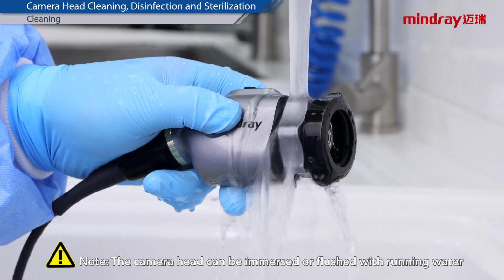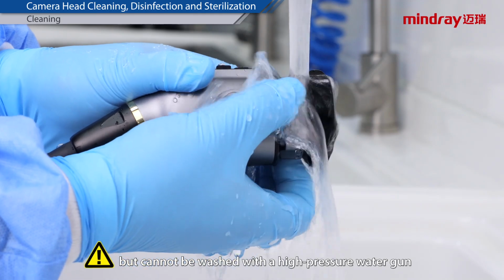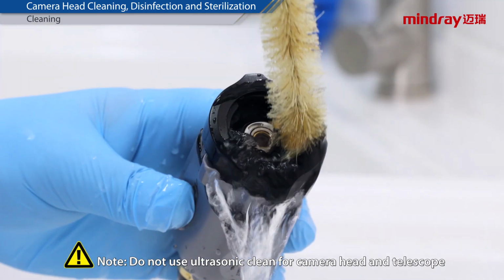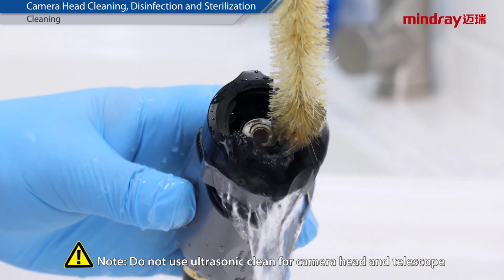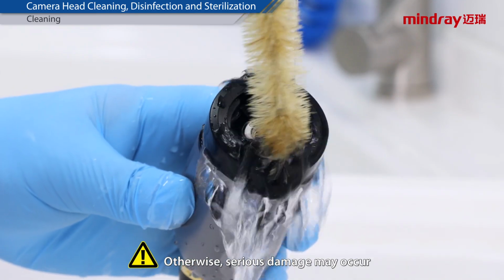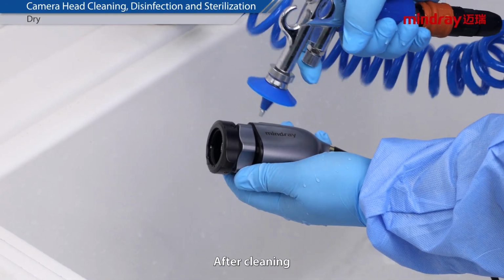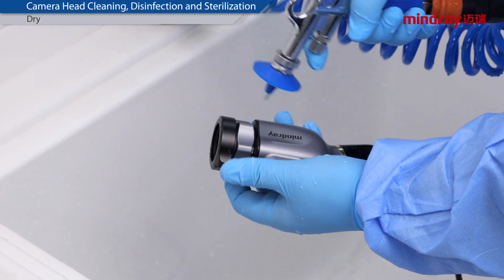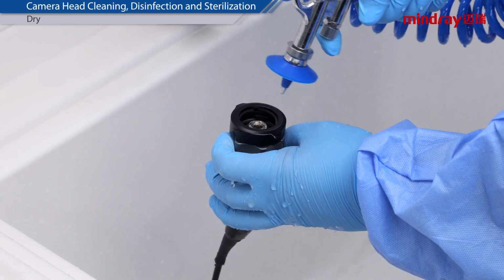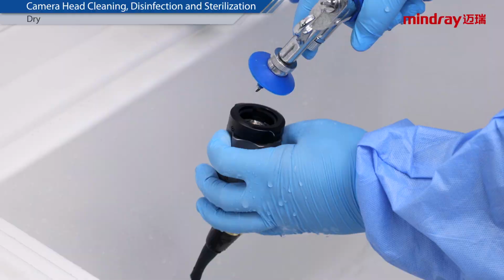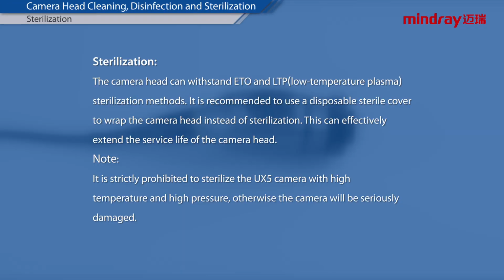Note: the camera head can be immersed or flushed with running water, but cannot be washed with a high-pressure water gun. Note: do not use ultrasonic clean for camera head and telescope. Otherwise, serious damage may occur. Dry. After cleaning, use an air pistol to dry the camera head. Sterilization. The camera head can withstand ETO and LTP, low-temperature plasma, sterilization methods. It is recommended to use a disposable sterile cover to wrap the camera head instead of sterilization. This can effectively extend the service life of the camera head.